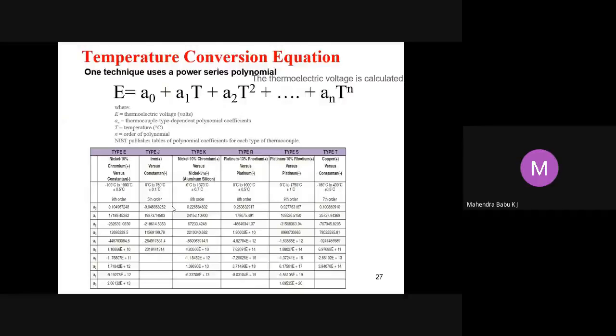For temperature conversion, here is one equation, a polynomial used to calculate the thermoelectric voltage: E = A0 + A1T + A2T² + etc. E is the thermoelectric voltage, An is the polynomial coefficient depending on the thermocouple type, T is the temperature in degrees Celsius, and N is the order of the polynomial. NIST publishes the polynomial coefficients for different types of thermocouples, as shown in the table.